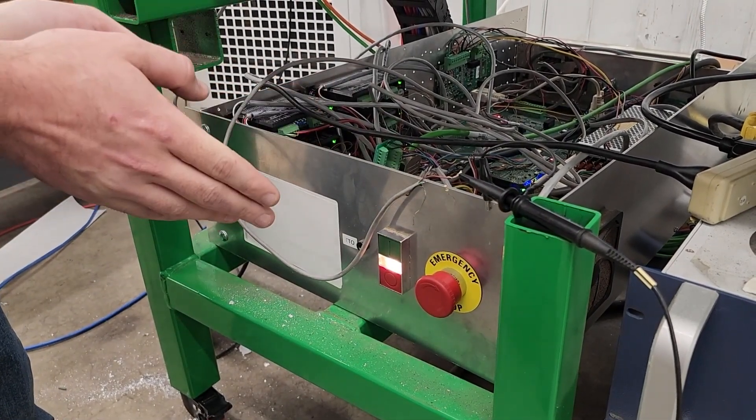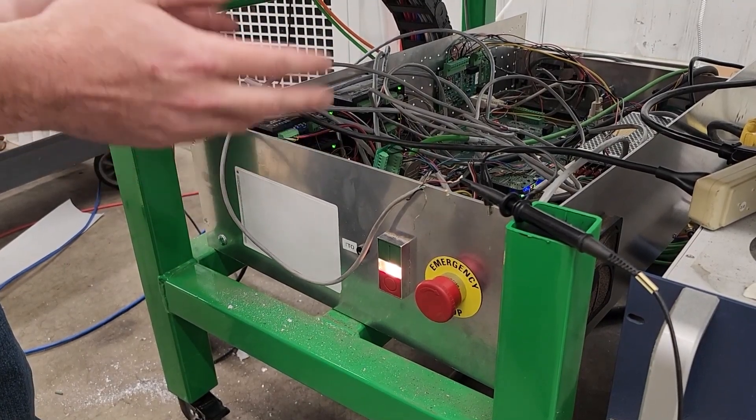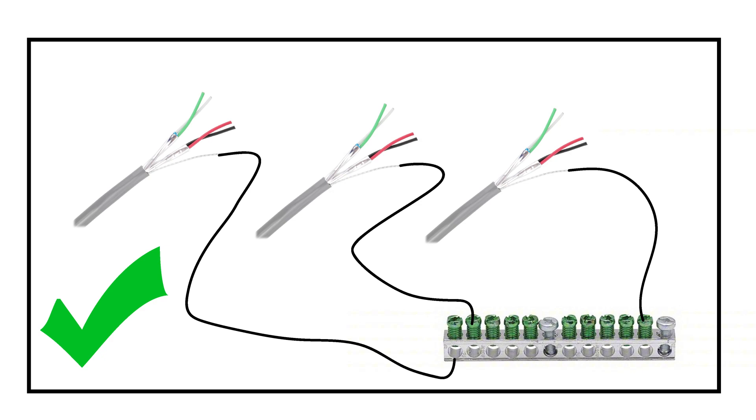And yeah, so this is really important in demonstrating why we need proper grounding in the cabinet. We want all those shields, all the grounds, going to one single grounding bus bar inside the cabinet.